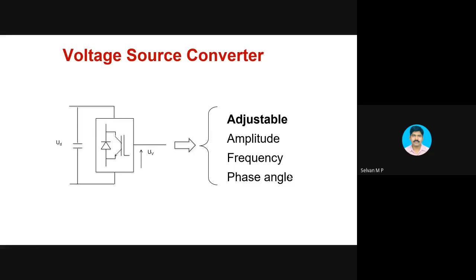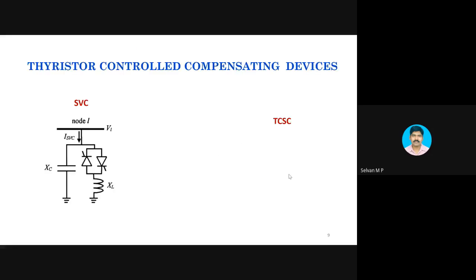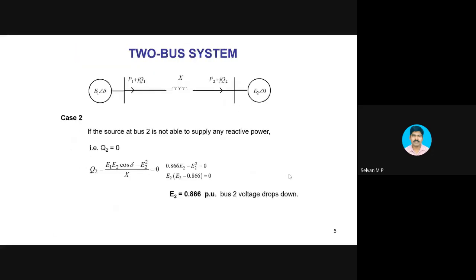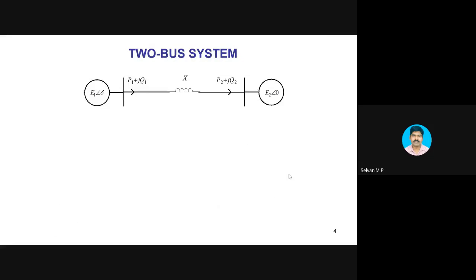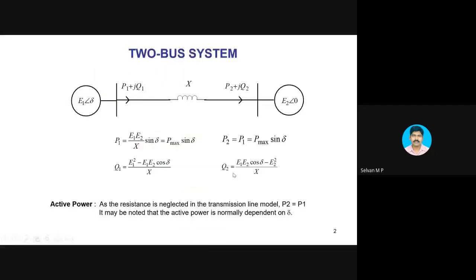Okay, in what way is this related to the discussions which I had in the previous slides? I said reactive power, reactive power, reactive power. Now I am suddenly telling that I have a voltage source inverter where I will be able to adjust amplitude, frequency, phase angle. Right? Why am I talking about this? Now you have to relate this voltage source converter with the second fundamental equation that I have written. Reactive power flowing in this line is dictated by the voltage of both the buses E1 and E2 and the angle between both the voltages.